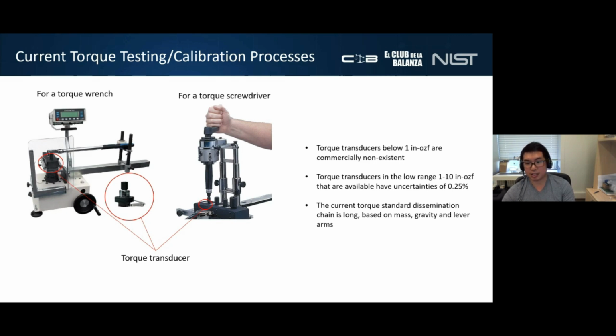These transducers can get pretty low, but nothing exists on the market right now below 1 inch-ounce force at a quarter of a percent uncertainty, or 0.25% uncertainty. These are all considered transfer standards as well, and none of them are primary, since you need frequent calibrations against mass and length.